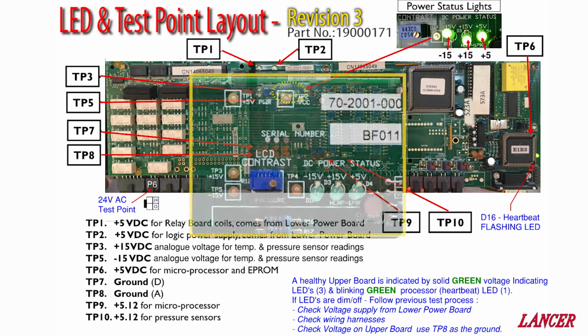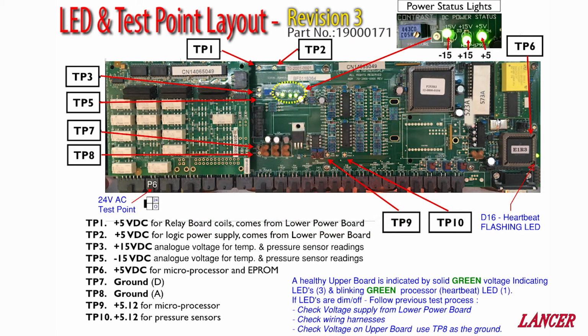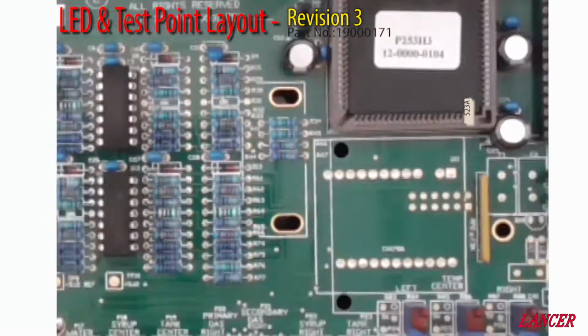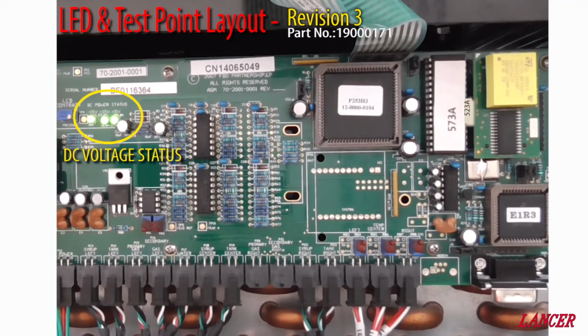Each of the test points are clearly labelled on the board. Ensure your multimeter has DC selected, if not in an auto ranging position. Then make sure you have a good contact with your probes, and specifically that you're using the ground on the upper control board, i.e. test point 8. The 24 volt AC supply to the upper control board does not have a test point or an LED indicator. If voltage confirmation is required, use the plug connected at P6, remembering to set your multimeter back to the AC range. This is a video of the board in a normal operating state.